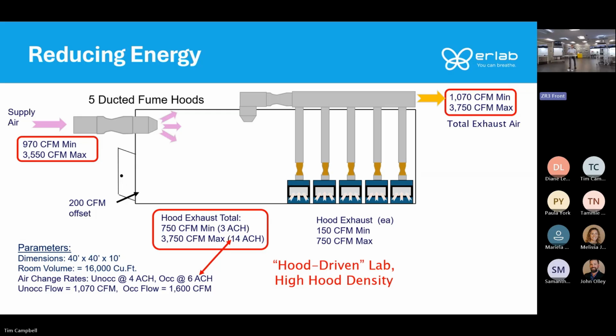So think about that. In the summer now, you have that hot and humid outside, so you have that dry air conditioned air in there. That's all being blown outside of the lab. Those 6 air changes would be enough to keep you comfortable. But now with those 14 air changes, that 8 extra air changes when all those hoods are in use, you're taking all that expensive dry conditioned air and blowing it outside, and you've got to bring in more of it. That's why it's very expensive when you overventilate the lab space.